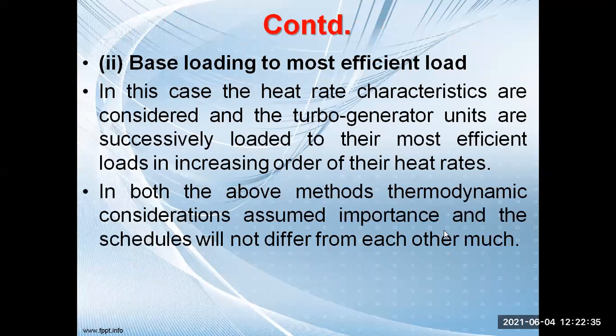Second is the base loading to the most efficient load. You have to understand the term. We have to base load to the most efficient load. In this case, the heat rate characteristics are considered and the turbo generator units are successively loaded to their most efficient loads in increasing order of their heat rates.